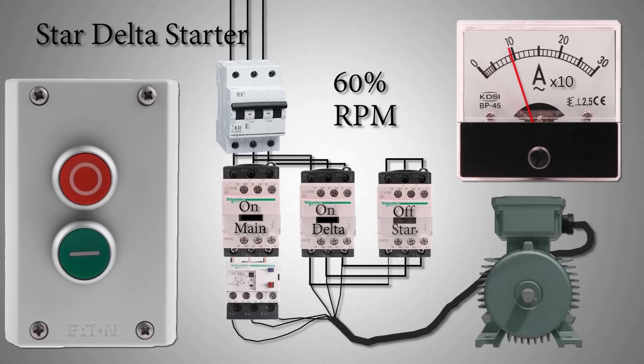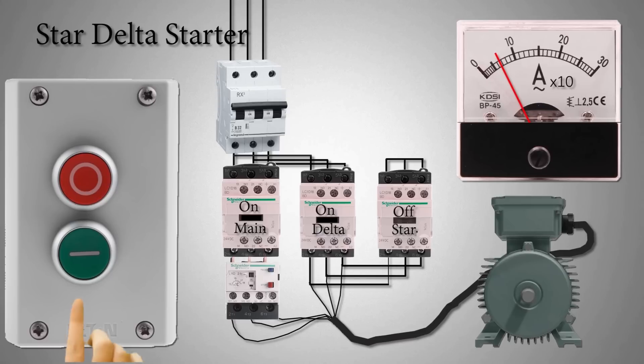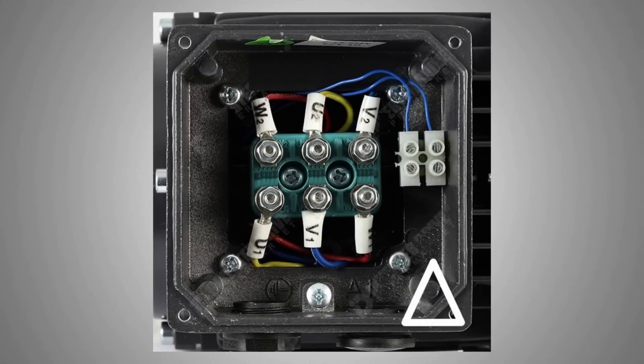Once the time is up, the star contactor turns off and the delta contactor turns on. This will reconfigure the motor winding to delta configuration, and full voltage is applied to the motor winding via the power and delta contactor. The motor then goes to its nominal speed. The reason why we use star-delta starting is to reduce the starting currents for big motors under heavy loads.